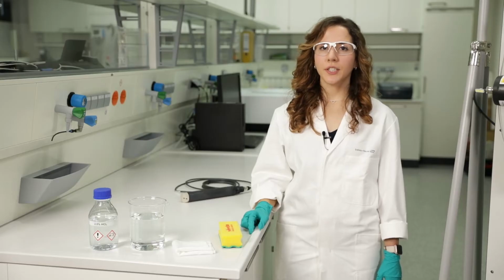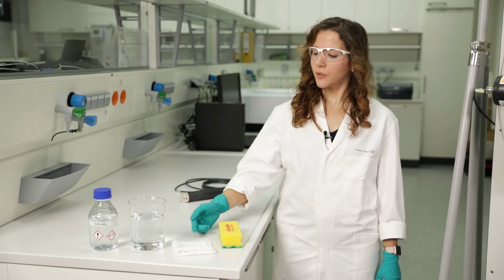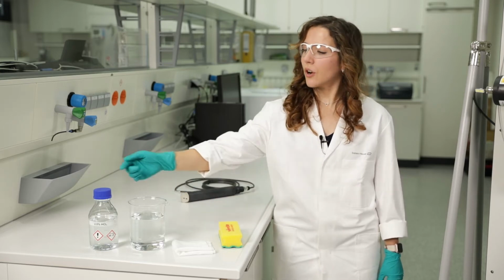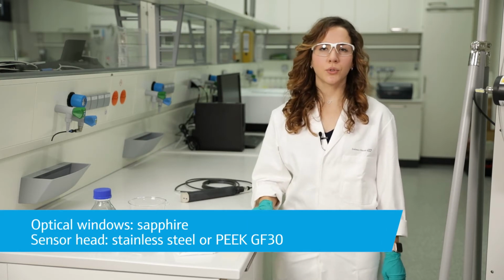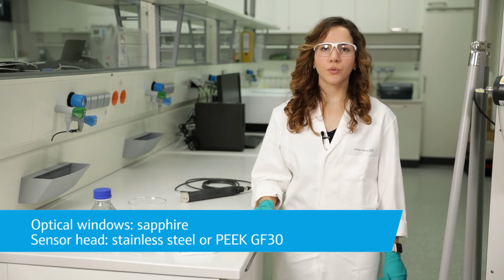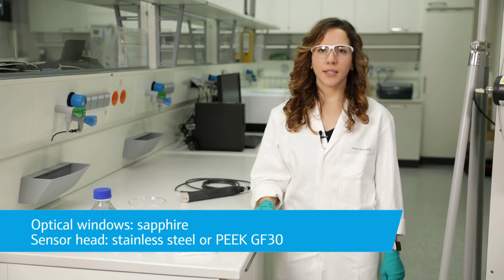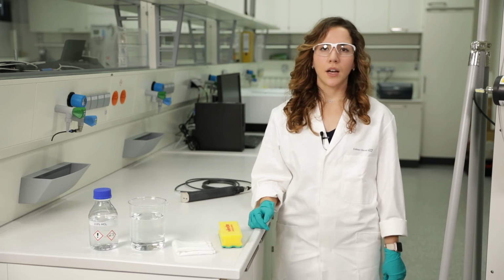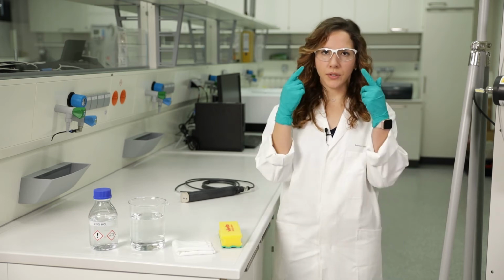For manual cleaning, you simply need a soft sponge or lint-free cloth and clear water or a cleaning solution. Although the sensor is robust due to the materials used, do not use sharp-edged objects like sandpaper for cleaning in order to avoid damages. And of course, please also wear your personal safety equipment and gloves. Before you take out the sensor for manual cleaning, set the sensor outputs in the Liquiline on hold, so that the measurement output is not affected by the cleaning.